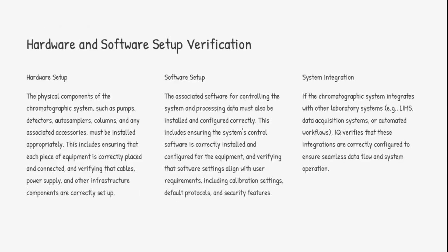Hardware and software setup verification ensures the physical components of the system, such as pumps, detectors, and columns, are correctly installed and connected. The associated software for controlling the system and processing data must also be installed and configured correctly. System integration verifies that the system operates seamlessly with other laboratory systems, ensuring consistent data flow and system operation.